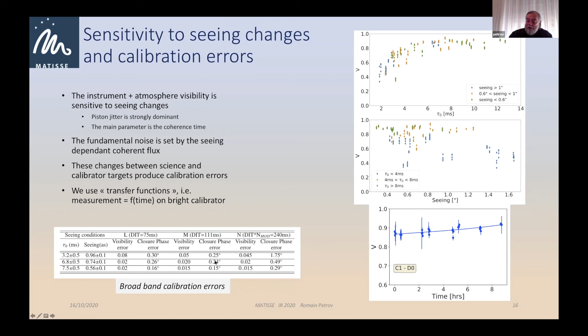And then for a given object, we monitor the broadband calibration error by making transfer functions, which are variations of the instrument visibility with different calibrators as a function of time. We either fit it or we simulate the science calibration to get the typical calibration error that we can have. And the panel here gives the values. In fair and good seeing conditions, the visibility accuracy is of the order of 2%. The closure phase accuracy is of the order of 0.2 or 0.3 degrees. Yeah, these are the broadband calibration errors which are implied.